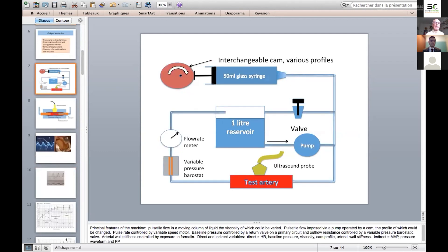To explain the nature of the machine, basically we have a fluid reservoir containing the fluid we're perfusing the vessel with. This is passed through a primary return circuit using a pump and a return valve by which we can produce varying input pressure, which goes into the test artery, flows through the test artery, and out through a variable pressure barostatic valve, which enables us to control the outflow resistance. Pulsatility is imposed on this column using a syringe operated by a cam.